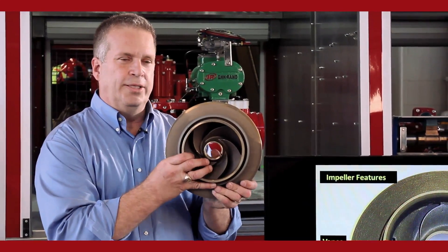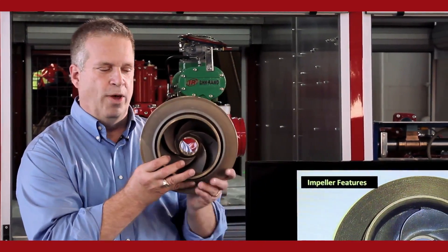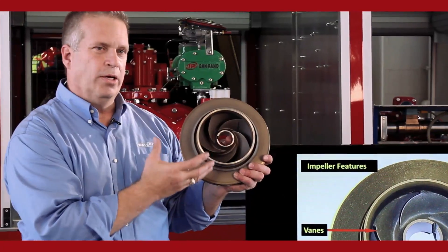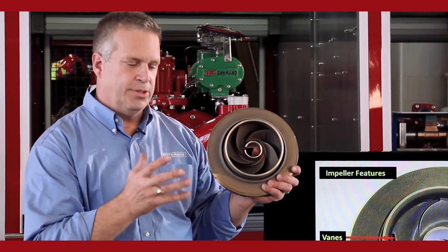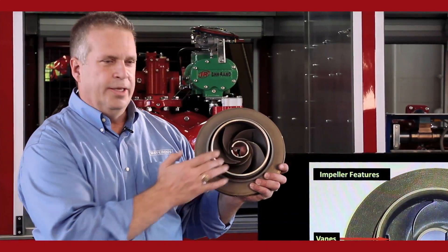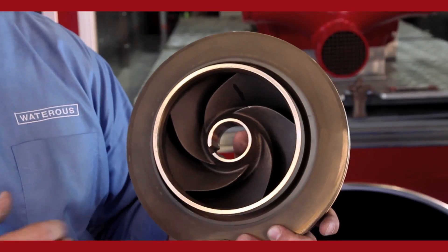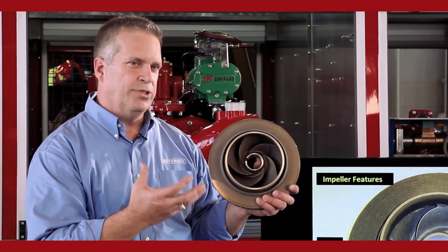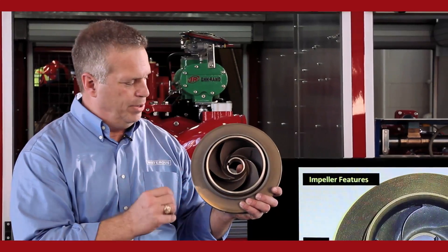Whenever the impeller shaft rotates, the impeller is going to rotate with it. Around the bore is the eye — this is where the water comes from the outside source. It comes in the intake side of the pump into the eye of the impeller. Inside the eye are five blade-like things; those are the vanes of the impeller, which create the centrifugal force to move the water out of the impeller.